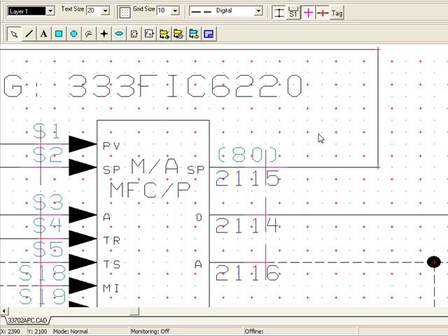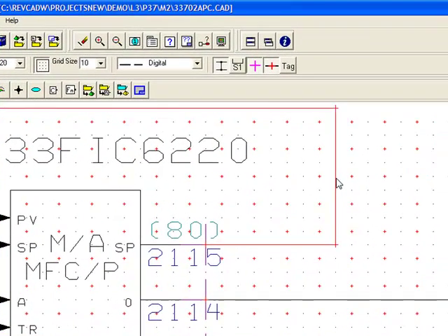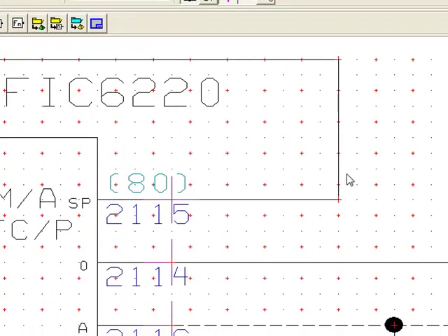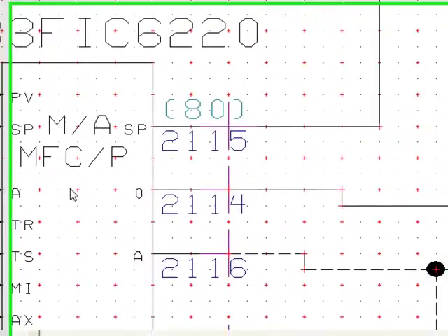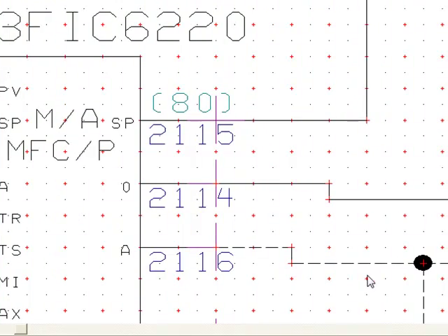Speaking of the grid here, this is a common problem that arises in a lot of WinTools and CAD EWS drawings, in that someone has drawn this drawing off of the standard 20 by 20 grid. So how can we fix that? Well, you can either go through and manually select each point and drag it till it coincides with the 20 by 20 grid in the red crosshairs in this example. There, now the block is on the actual output.